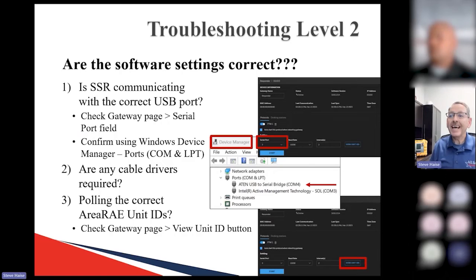Number 2: are any cable drivers required? Using Device Manager, while confirming you're connected to the right COM port, also check there are no warning bubbles under that port in Device Manager. If you're missing the Windows driver to run that patch cable, your computer won't be able to communicate with your RAE 3 host. That's why we ran the day 0 call this morning, to ensure you have that cable driver installed. If you ever need it again, it's linked on the Allsafe Industries webpage, and we'll gladly share it with you again.